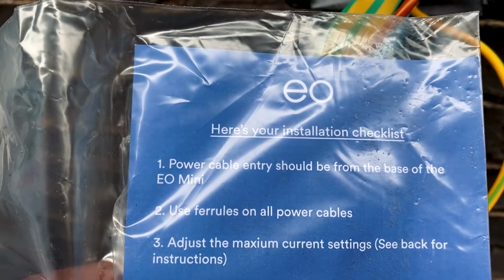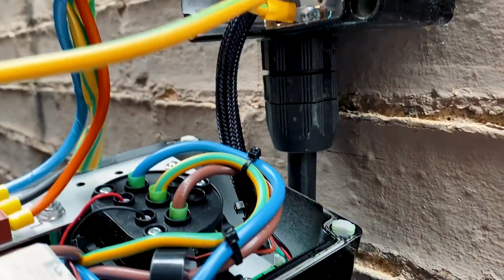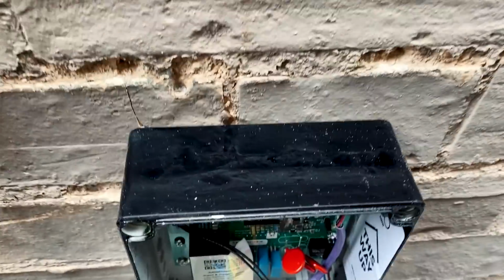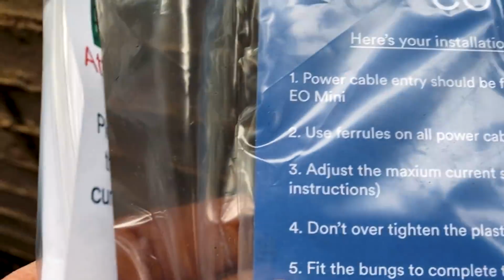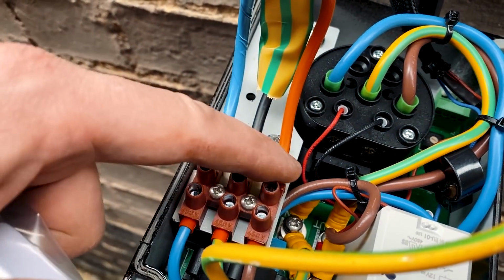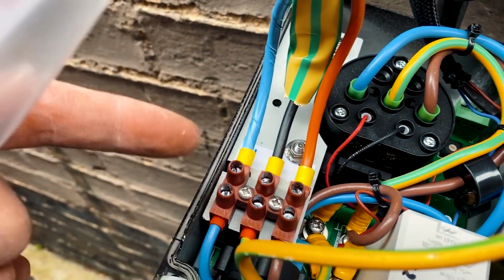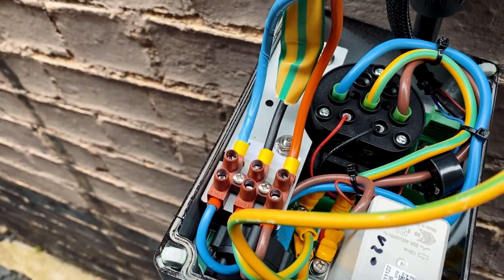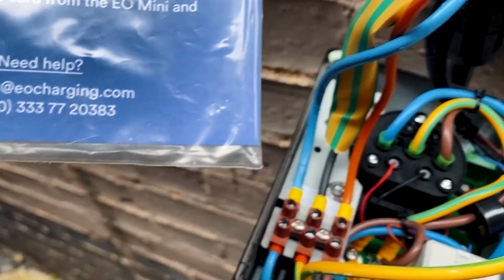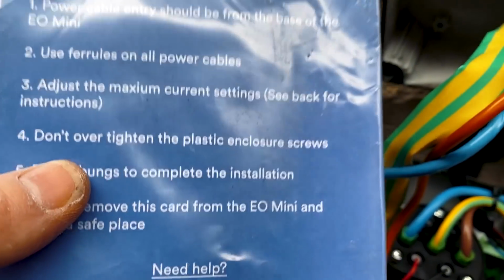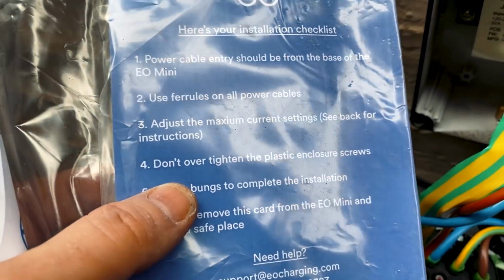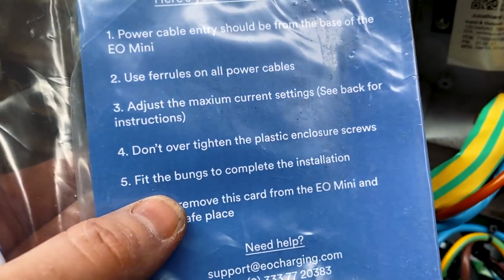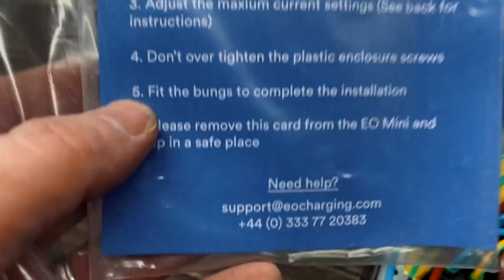Also, the instructions mention that the power cable entry should be from the base of the EO Mini Pro, which is what I've done - you shouldn't take it in the top or the sides. You should also use ferrules on all power cables, which is what I've done here - that's just good practice anyway. And you shouldn't over tighten the plastic screws that screw it in here, and you should fit the supplied bungs to seal it off properly.